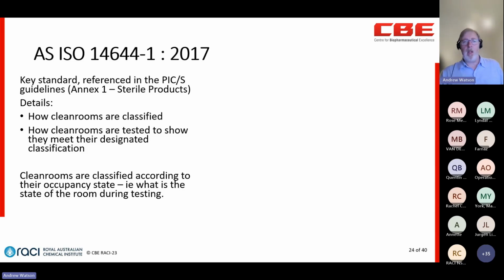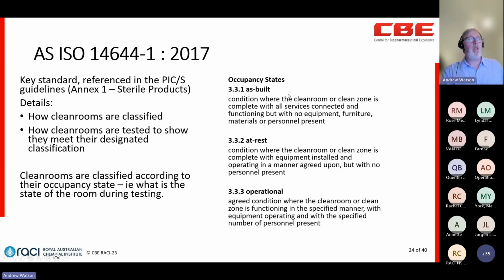8 clean room, an ISO 5 clean room, or whatever. It actually matters a great deal what is actually happening in that clean room as to what that classification is. And that's based on what we would call our occupancy state. So there are 3 occupancy states: as built, which is essentially what the actual room is; at rest, which is what contribution the room and the equipment make to the cleanliness of the facility; and operational, which is where it's operating in its regular manner, or sometimes, under PICS GMP, we talk about operating at risk.